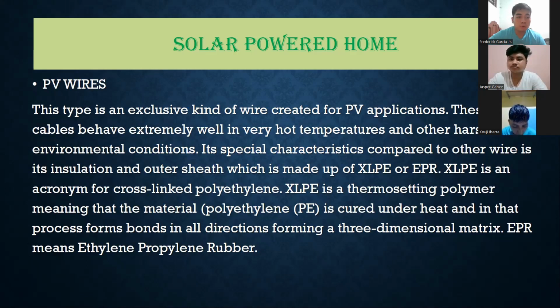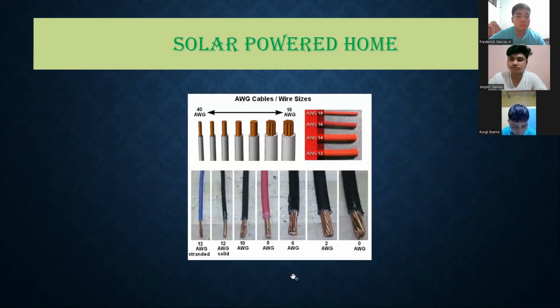XLPE is an acronym for cross-linked polyethylene. XLPE is a thermosetting polymer, meaning that the material, polyethylene, PE, is cured under heat, and in that process forms bonds in all directions, forming a three-dimensional matrix. EPR means ethylene propylene rubber.